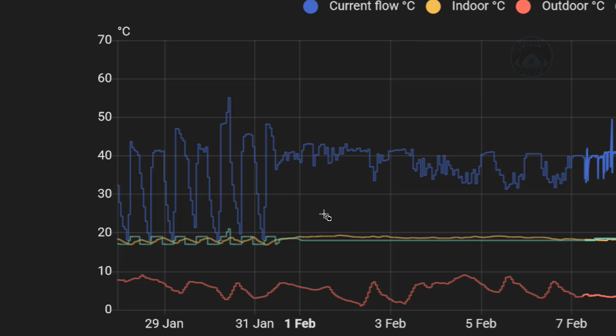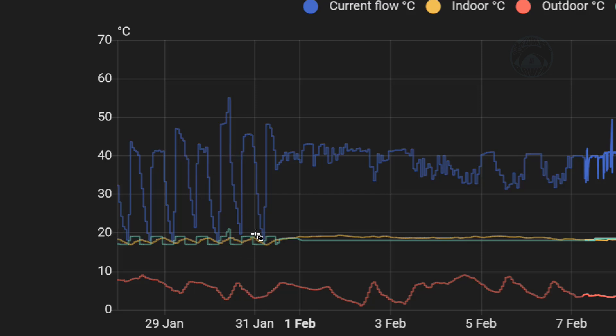With inactive, the boiler was on constantly, using more gas and costing more money — though not a lot more. It was around six pounds ten or six pounds twenty a day, and on two extremely cold days in January where the temperature dropped below zero, it cost seven pounds fifteen. With expanded, running on and off for the 10 days, we were getting around three pounds fifty a day, four pounds twenty at the very highest.